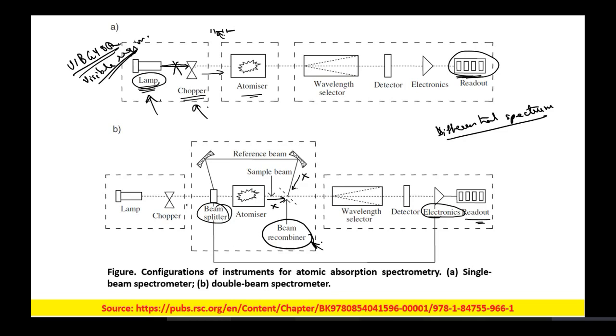In the double beam, there are two beams: one passes through the sample and the other is redirected to the reference beam. The beam coming out of the sample is called the sample beam and the redirected beam is called the reference beam. Both sample and reference beams are recorded and the differential spectrum is calculated.